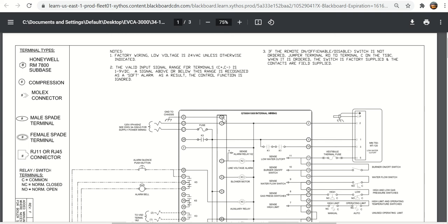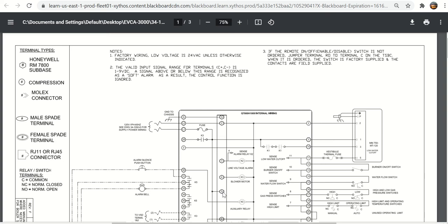If you remember on the traditional flame safeguard, every flame safeguard has a G terminal for ground. Here is terminal number two on the flame safeguard. That's the neutral and you follow the fuse down here and there is terminal number five on the flame safeguard. That is the power terminal. If you looked at a traditional flame safeguard, the RM7896D model, you would see that terminal number five is labeled as 120 volt power. Terminal number two is neutral and G is ground.